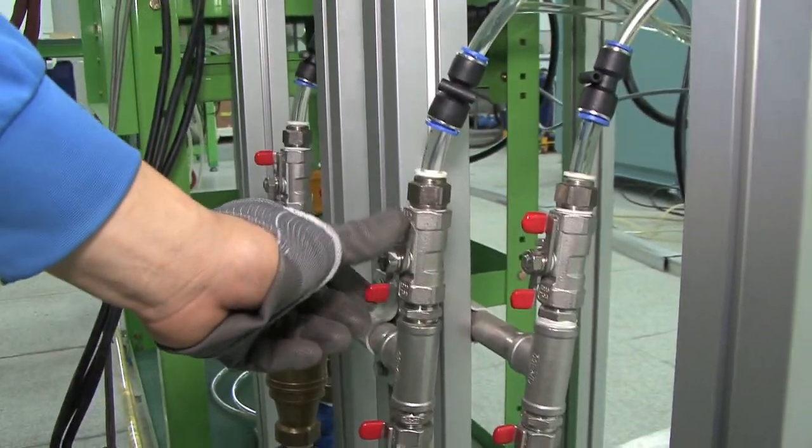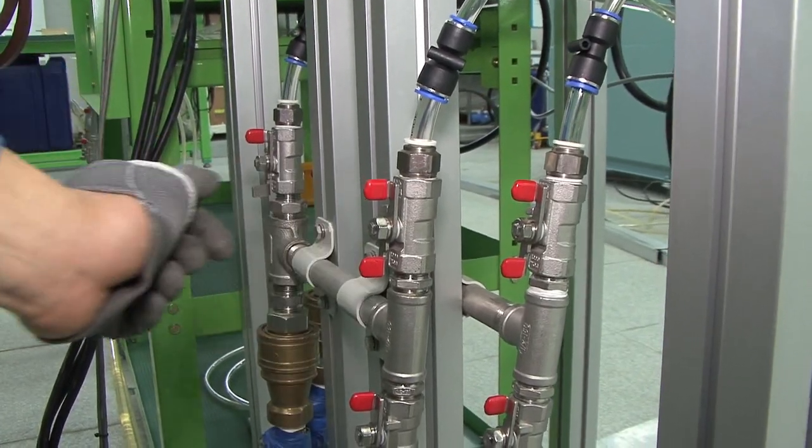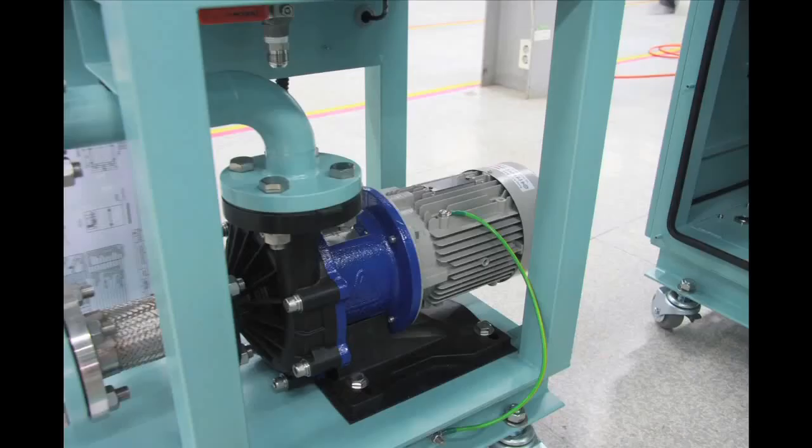Open the valve installed in the inlet and outlet of FTU. Refer to checkpoints before operation. Check leakage from FTU tank and ECU, PRU, cooling pipes. Supply cooling water, fresh water, if the cooling water is insufficient. In case of long-term storage. If the same problem persists, please contact the manufacturer.